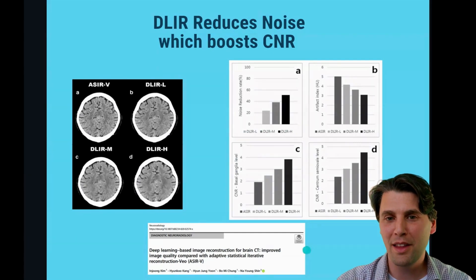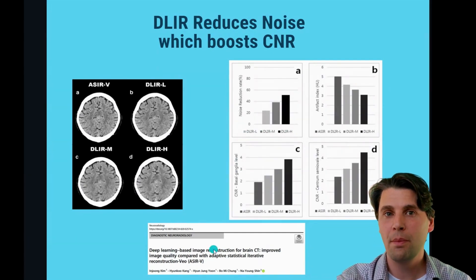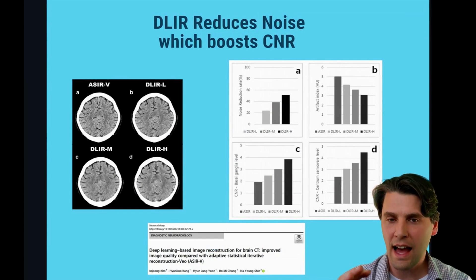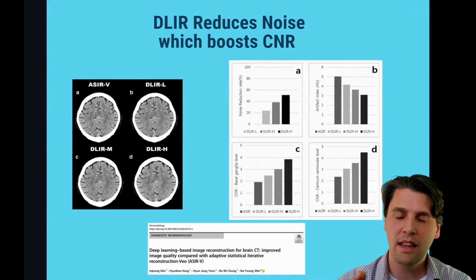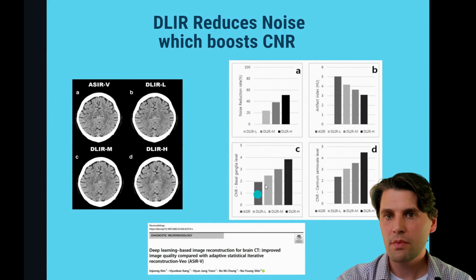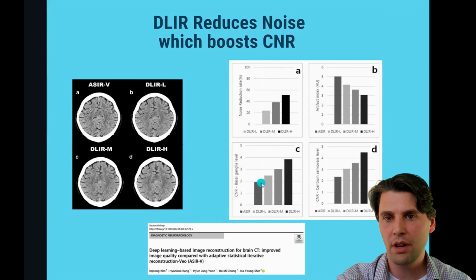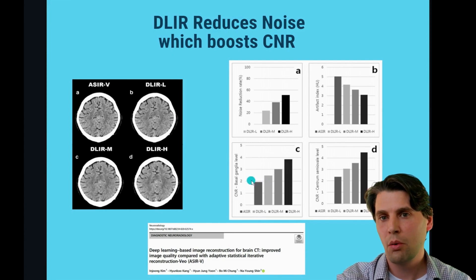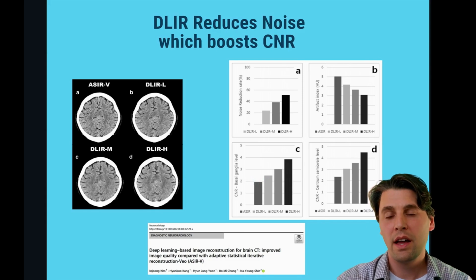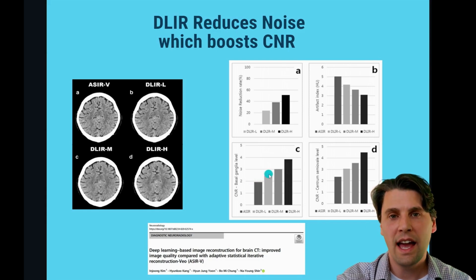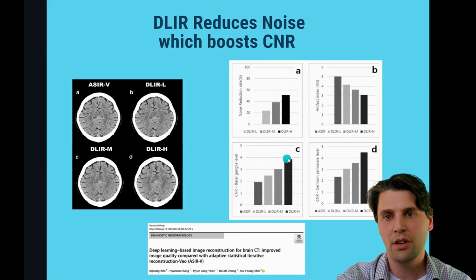This is from Kim et al. They looked at neuroimages and they looked at the standard ASIR, which they were using at their facility, and then performed the contrast-to-noise ratio measurement. The contrast-to-noise of these clinically relevant differences in soft tissue was close to two in the case of the ASIR images, and then it was significantly increased for each level of the deep learning image reconstruction, up to a little bit less than four. So you can see there is significant improvement in the contrast-to-noise ratio.